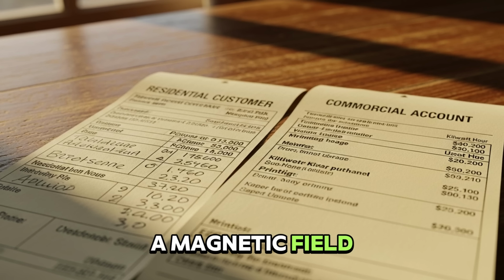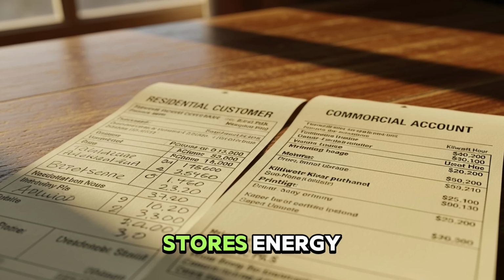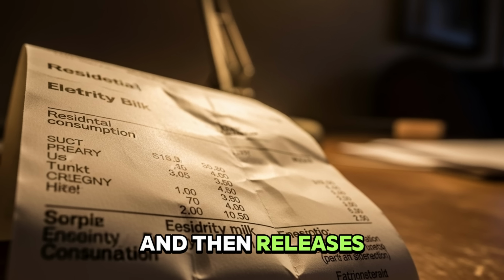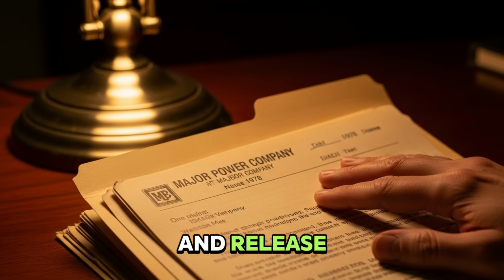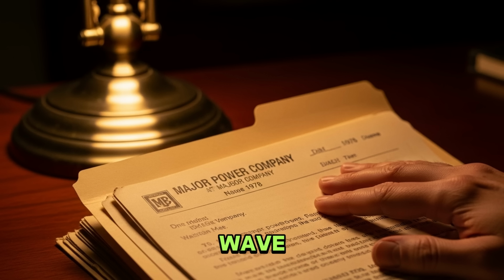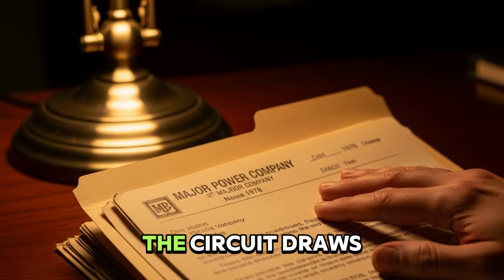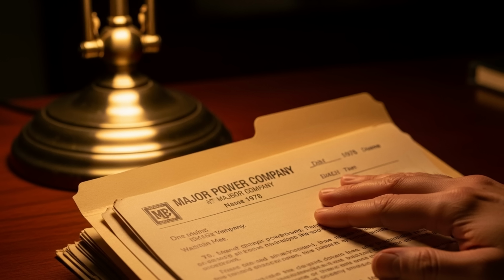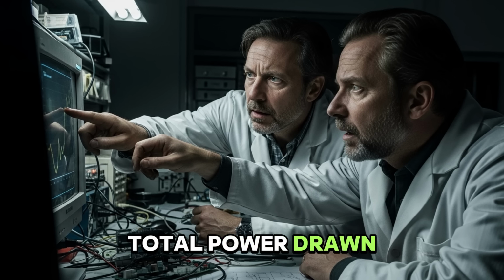Inductive loads create a magnetic field as part of their operation. That magnetic field stores energy during part of the AC cycle and releases it during another part. This energy storage and release causes the current wave to lag behind the voltage wave. They fall out of phase. When current lags voltage, the circuit draws more current than it converts to useful work. The ratio of useful power to total power drawn is the power factor.